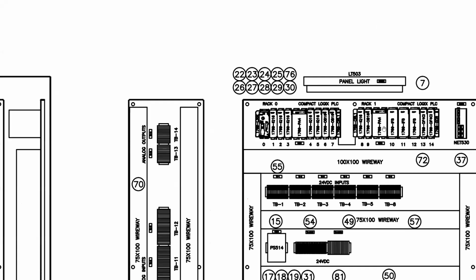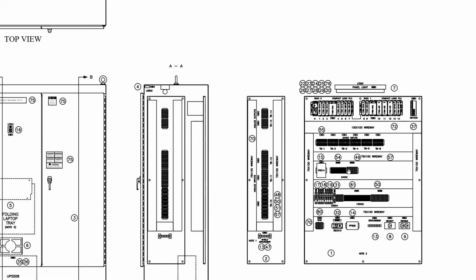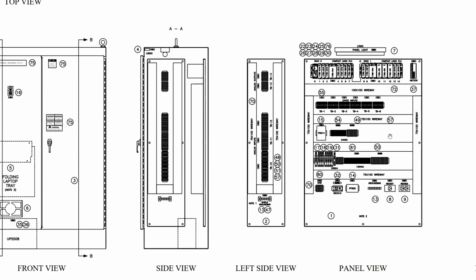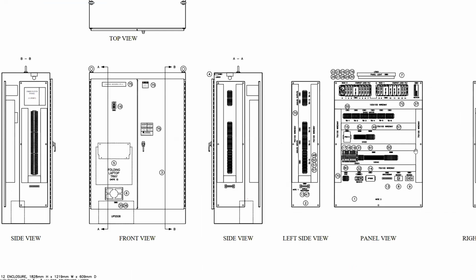You've got your PLC here. They've done a nice job of labeling the actual cards. So that's a 1769 IQ16. That's an Allen Bradley CompactLogix product line. You can see they've got side panels as well. So not everything fit in the back plane, or potentially this client needed additional shielding. So they wanted to separate their analog inputs from the rest of the power.